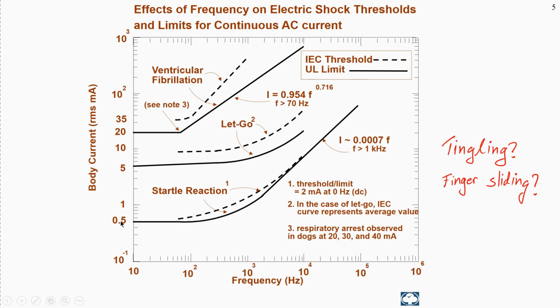They're talking about 0.5 milliamp. These are frequencies, and as you can see, the sensation or danger is higher at lower frequency than at higher frequency. The reason is that at much higher frequencies, the current passes through your skin and doesn't penetrate. So at low frequency it's more dangerous if the current is high. So we have a limit here of 0.5 milliamp — this is the startle reaction.